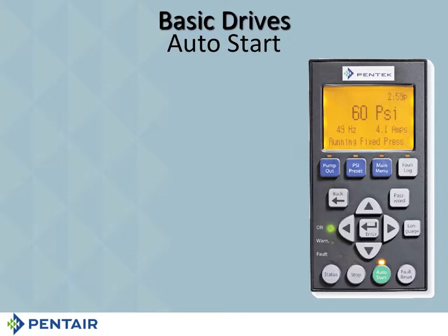Now, auto start. You'll notice when you push the button, the on light is going to be on. There's power to the system. And when you push the auto start button, that's going to turn that light on. Now, the first thing that's going to happen, it's going to go up to 45 hertz and then slowly build. All right? It'll tell you what the amps is. It'll tell you you're running a fixed pressure. And you'll notice the key's not on this one. So we're doing original setup here.